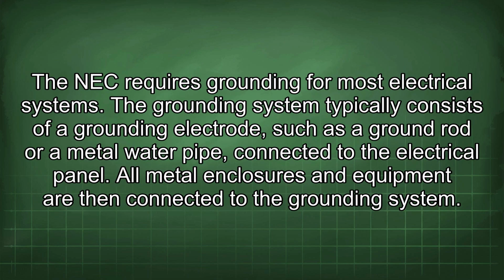The NEC requires grounding for most electrical systems. The grounding system typically consists of a grounding electrode, such as a ground rod or a metal water pipe, connected to the electrical panel. All metal enclosures and equipment are then connected to the grounding system.